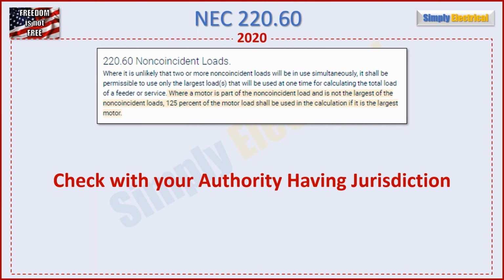But you're going to have to be careful though, because due to the unclear wording of the text, this may vary from place to place. Different jurisdictions will undoubtedly interpret this differently. If you're using this in the field, you'll have to check with your own jurisdictional authority to know how they are interpreting Article 220.60. Now, if you're taking an exam, they usually give you hints as to what they expect. If they tell you what the largest motor load is in the building, they likely expect you to take it into consideration in your calc.